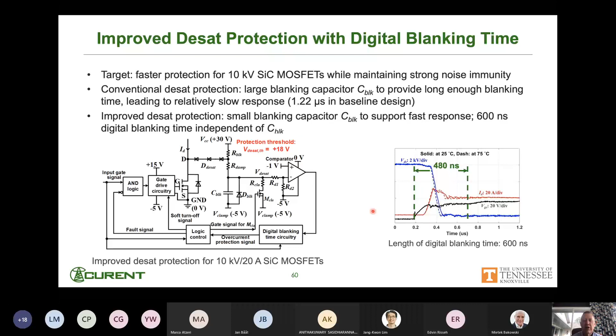Response time for hard switch fault is typically determined by that digital blanking time, because you're switching into a fault and it rises very quickly. If that's during your blanking time, once that blanking time ends, you're going to detect that fault immediately.